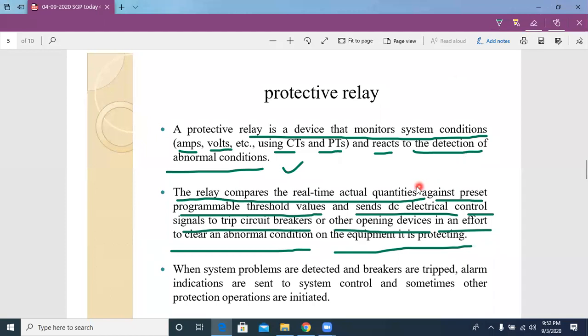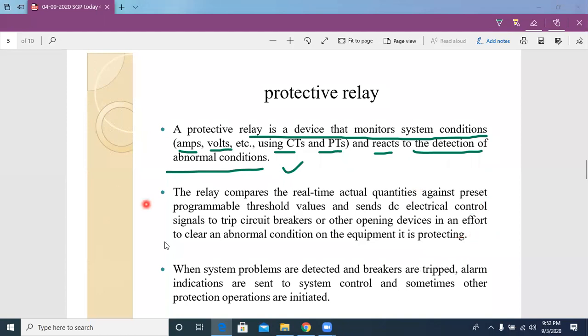So what they said is, let me consider the relay activating quantity is current. Here the relay activating quantity is current. So this relay always compares this current value, that means the real current value, with its preset value. So when a difference takes place, it sends a signal to the circuit breaker. When the circuit breaker gets a signal from the relay, it operates.